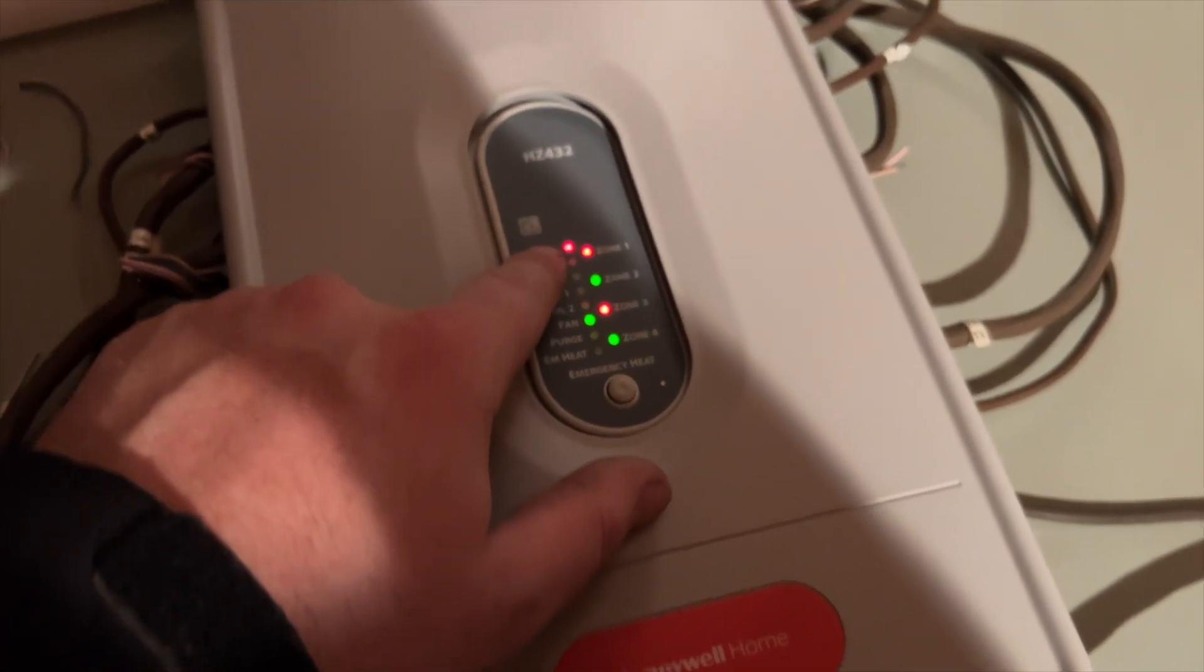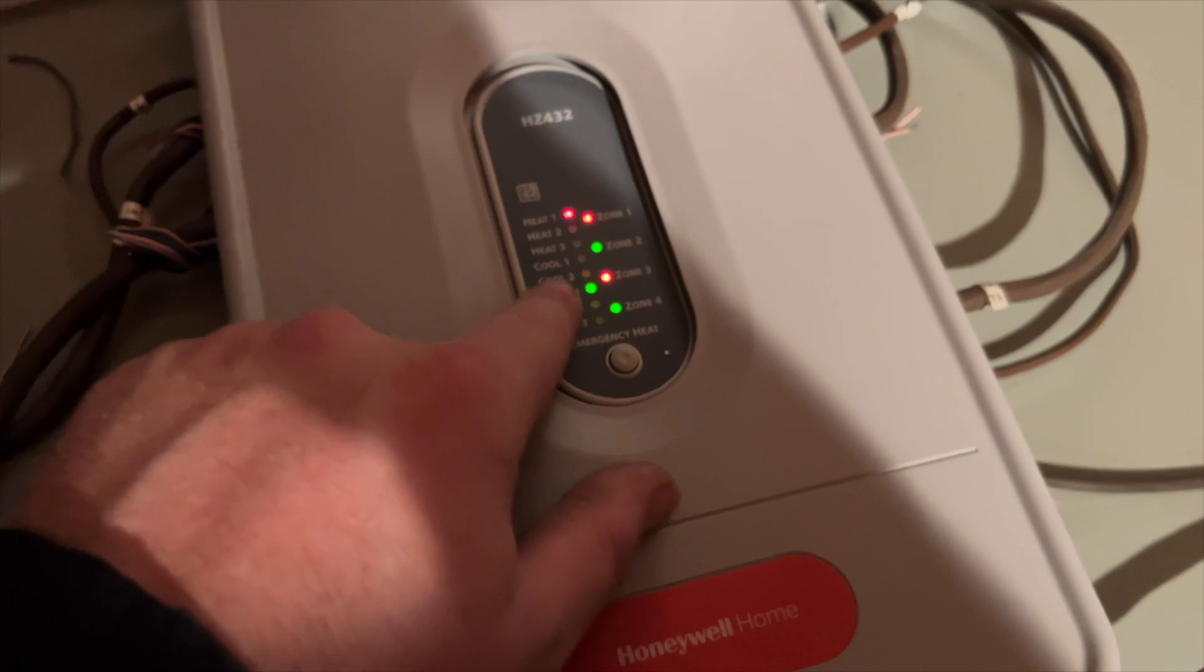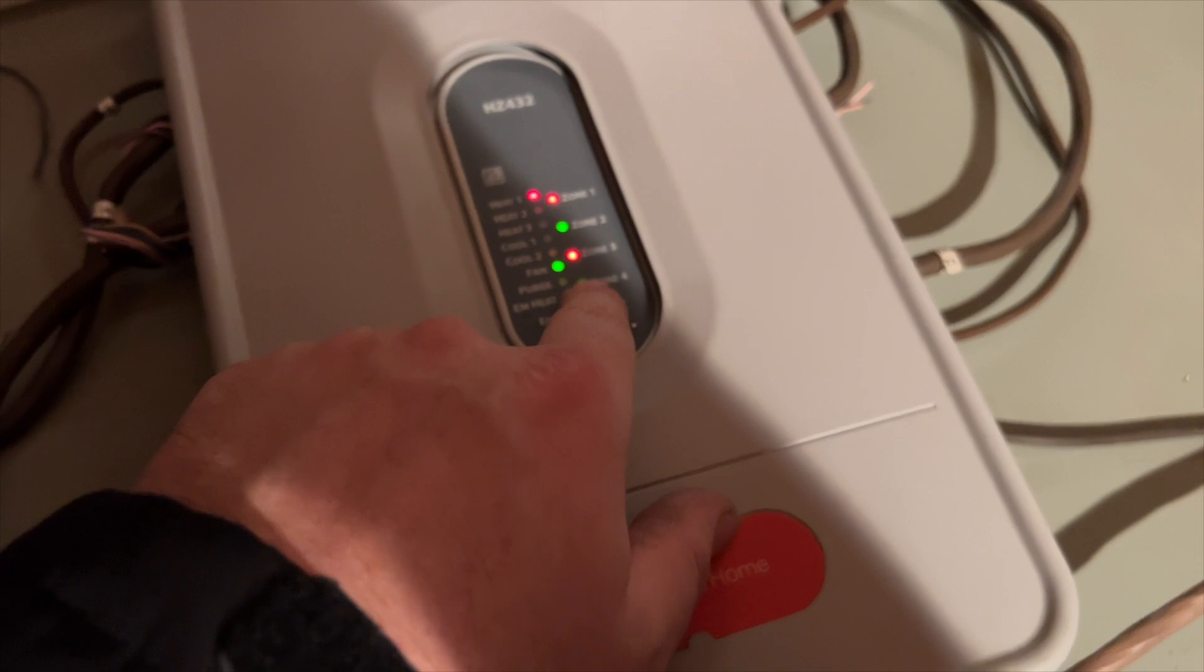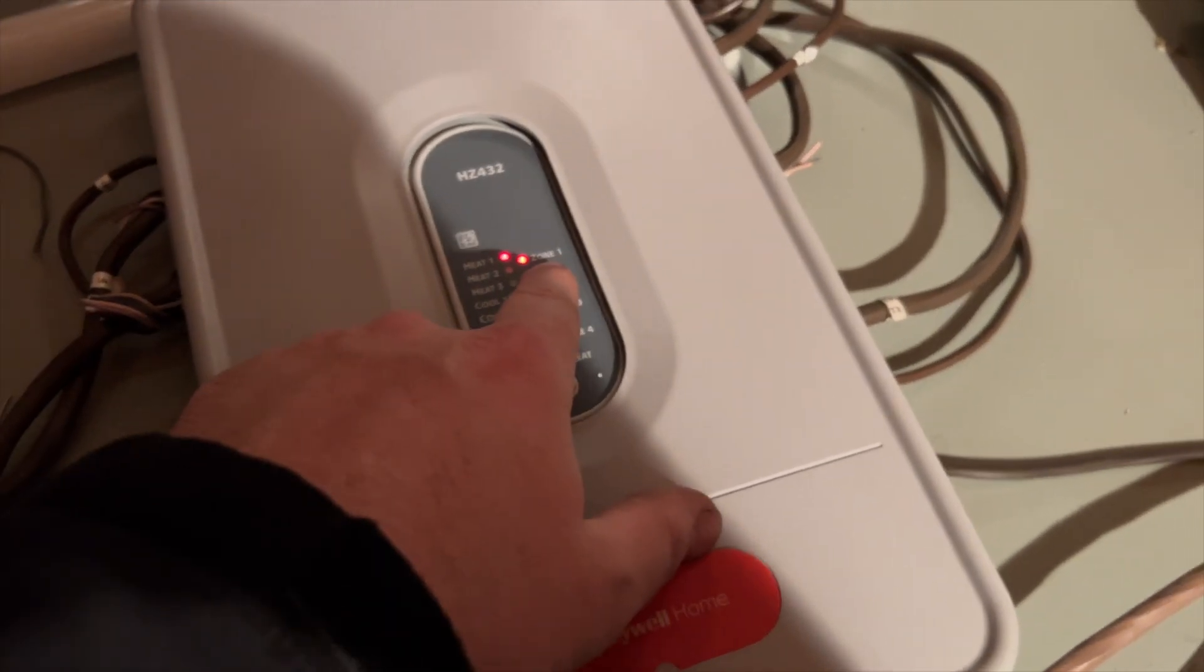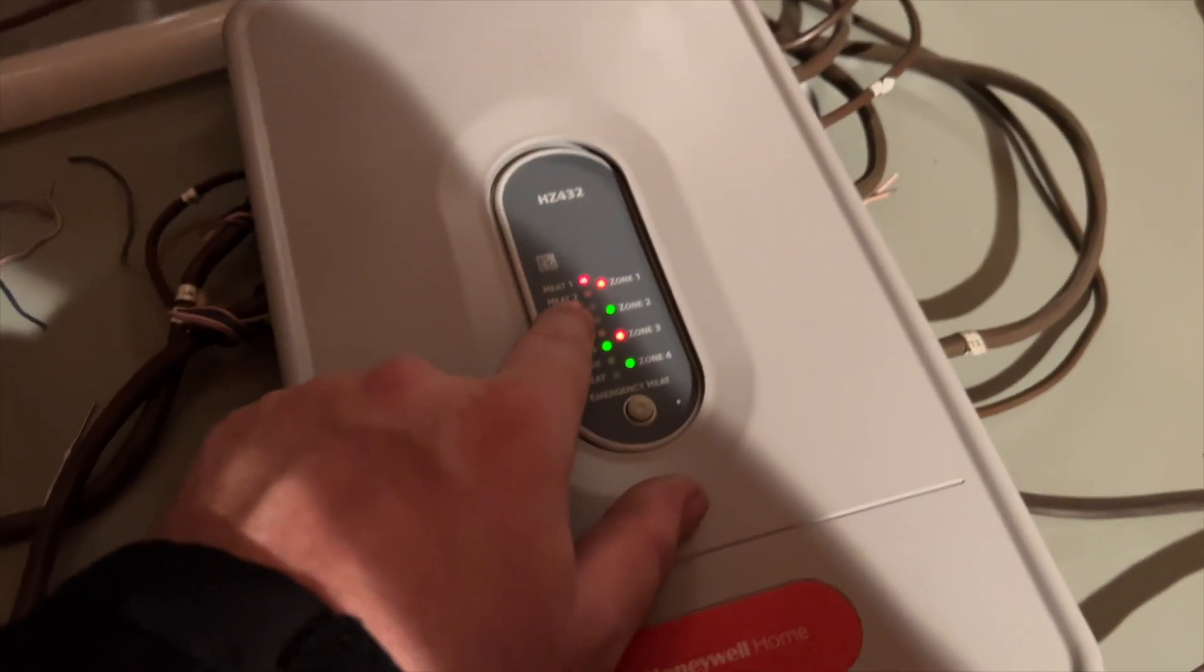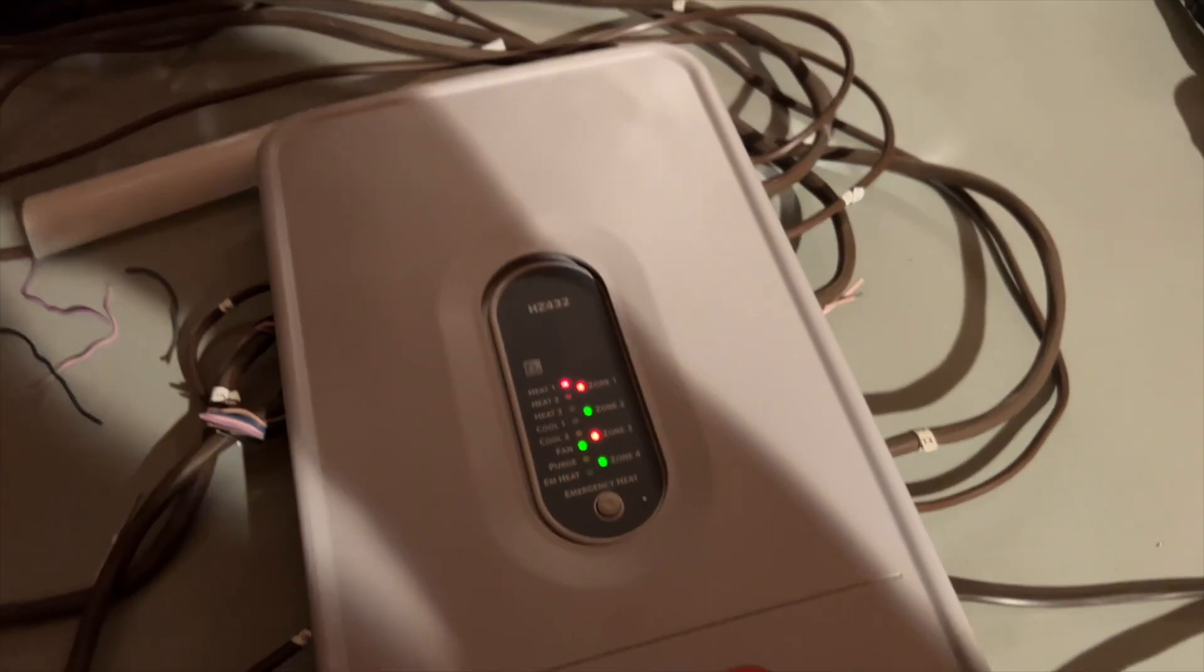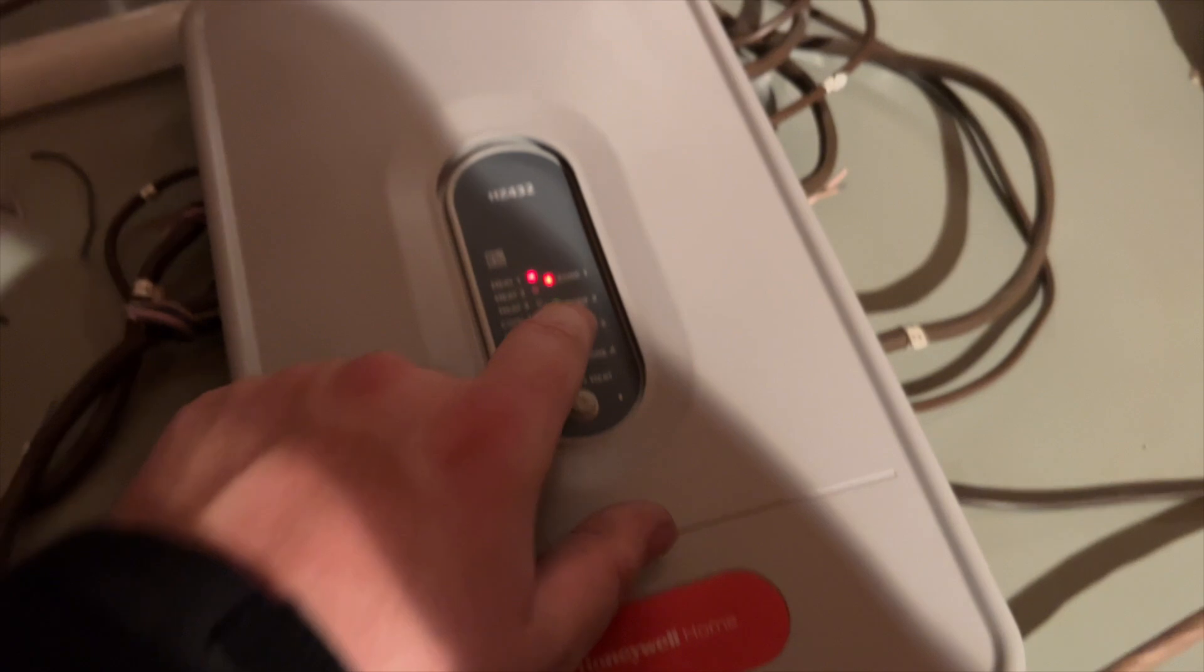So red means it's heating. Anything red means it's on. Or I'm sorry, red is for heating. For the zones, if it's green that means it's open. If it's red, that means it is closed. If it is closed, it's sending 24 volts to the zone damper. If it's open, there's no power because it's spring open.